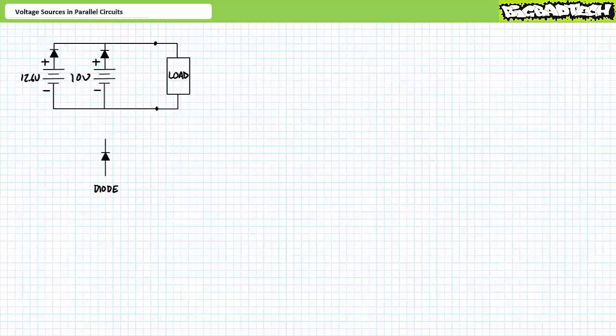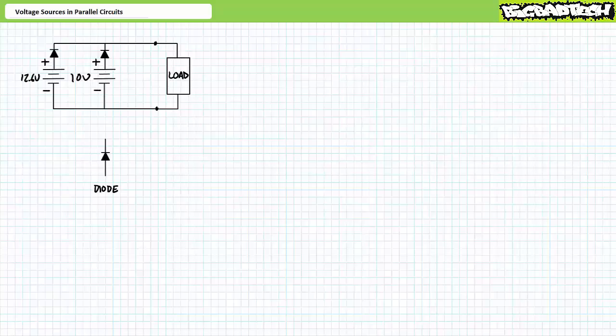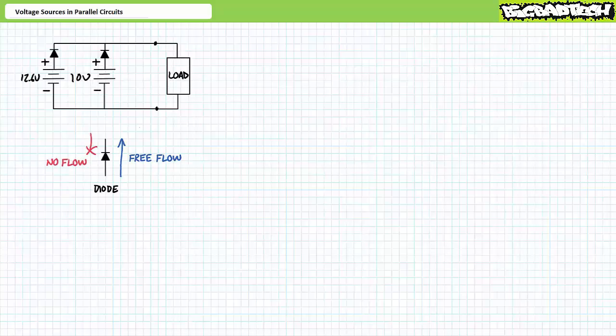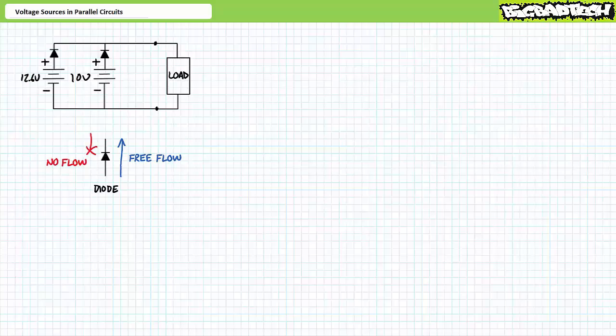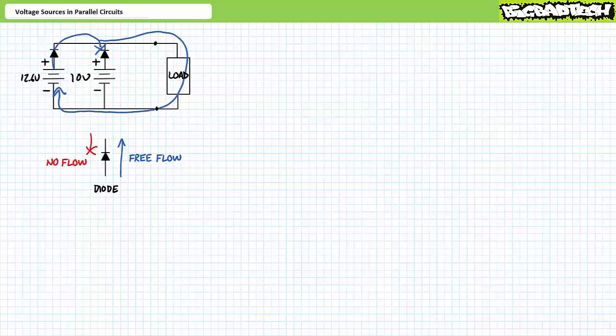A common method of preventing this is the incorporation of a semiconductor device, known as a diode, in series with each battery in the battery bank. We'll examine diodes in greater detail in later lectures, but for now, you can think of them as the electrical equivalent of a check valve, which permits current flow in one direction only. The arrow on the diode schematic symbol indicates the direction of free flow, whereas the wall indicates the direction of no flow. Configured in this fashion, each battery in the battery bank is permitted only outgoing flow and will not allow incoming flow. This would prevent the fresh battery from discharging due to the deeply discharged battery in an uncontrolled fashion.